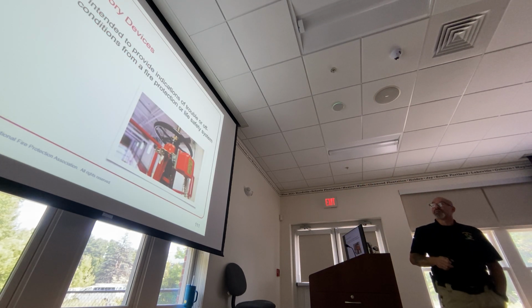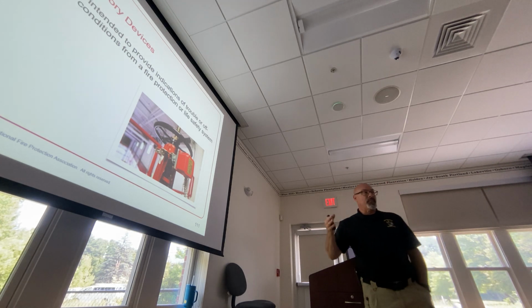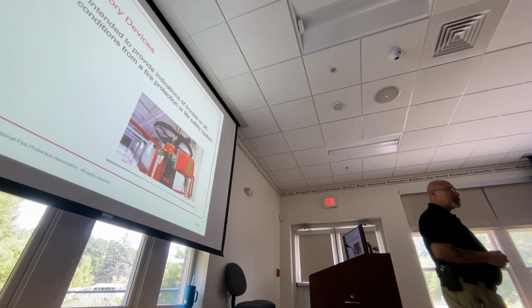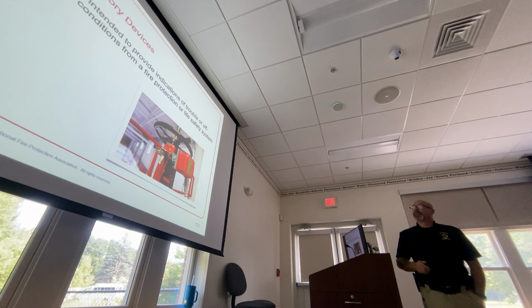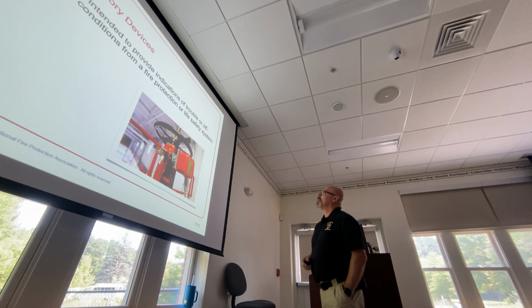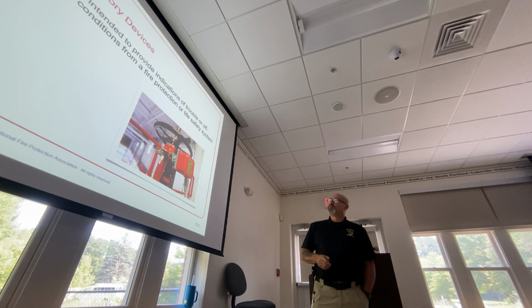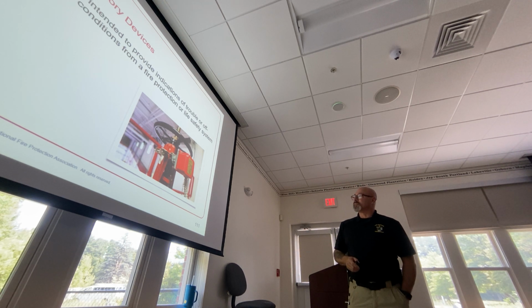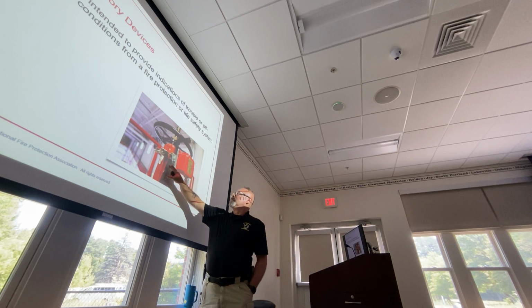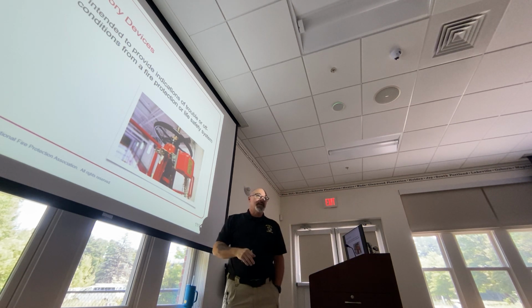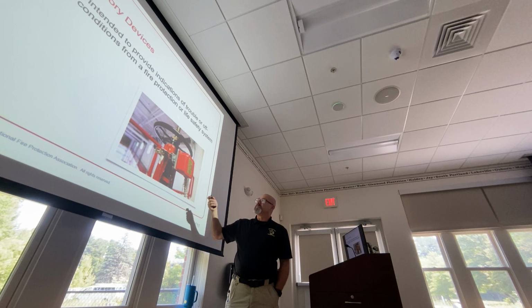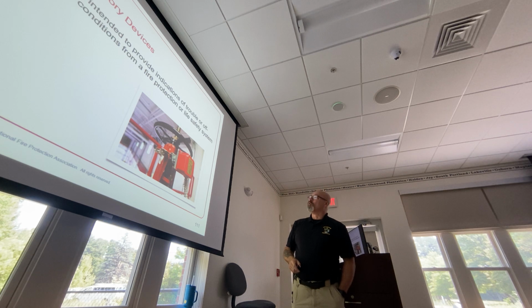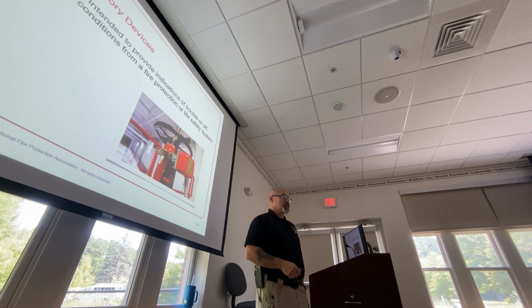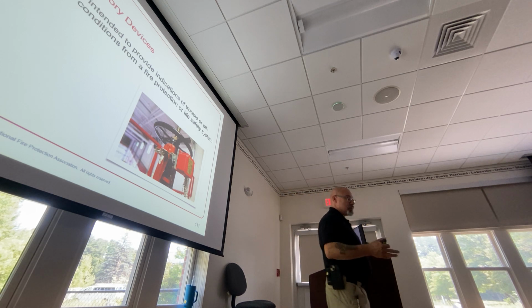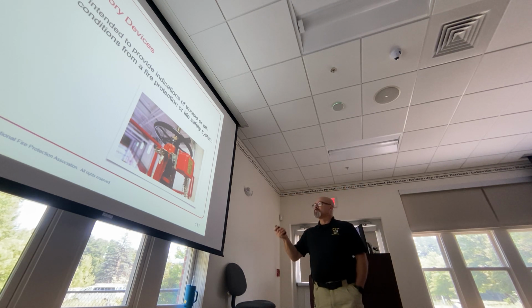All right, so we already talked about supervisory devices, but when we're talking about detection and alarm systems, we're talking about supervisories that are devices intended to provide indications of trouble, of off-normal conditions from a fire protection or life safety system. Something happens to this valve, it's gonna send a signal. That's a trouble. If somebody operates this valve, that is an off-normal condition, okay? Somebody closed the valve or opened it or tried to or played with it. That's supervising that valve.